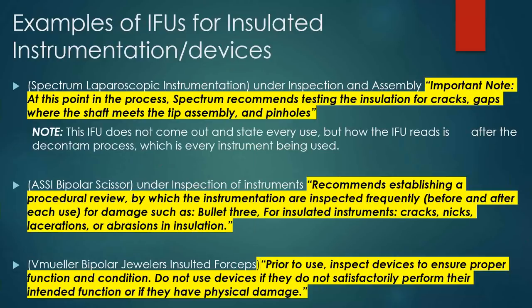The next bullet is your ASSI, accurate surgical instrumentation, talking about a bipolar scissor. It states it recommends establishing a procedural review by which the instrumentation is inspected frequently before and after each use. Here it defines exactly when, for damage, and under bullet three, for insulated instruments: cracks, nicks, lacerations, or abrasions in the insulation.